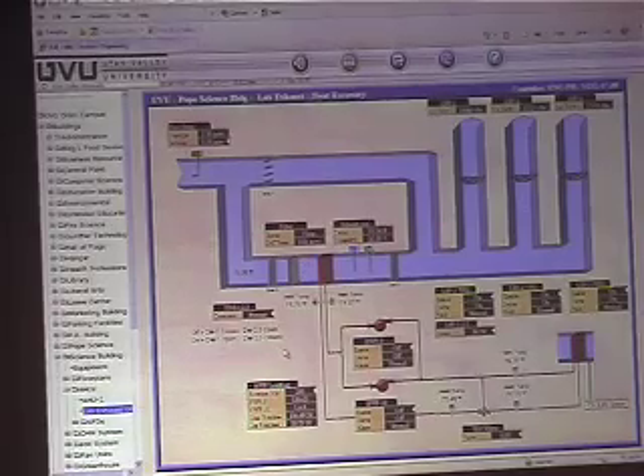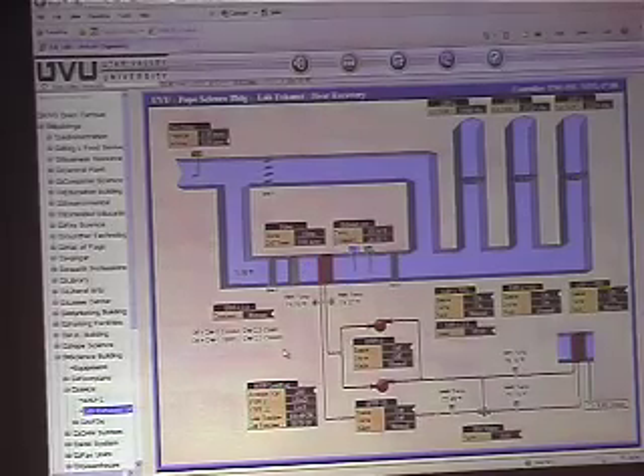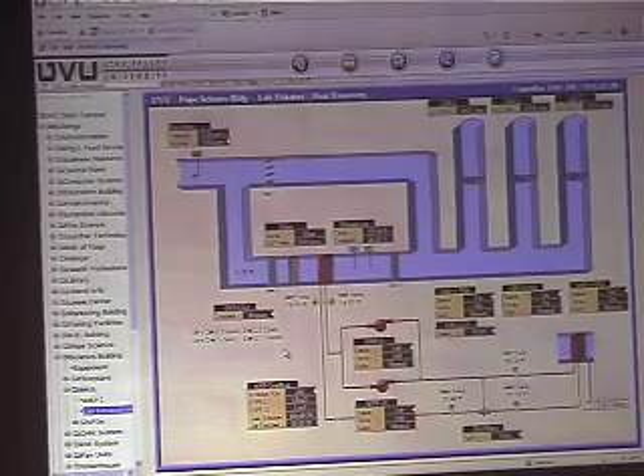Those three big fans are tied directly just into the fume hoods only? Is there more, do they pull more from the building? They're tied into the exhaust valves, yeah. The exhaust valves feed the hoods, as well as there's exhaust in the room, hoods, right? And then you've got a general exhaust in the room. So when the hood's open, the general exhaust comes down and vice versa, because we're trying to maintain an offset in the room. Just one duct for the general exhaust in the room? Some of them have two exhaust valves in the room. It just depends on the room, the size of the room.